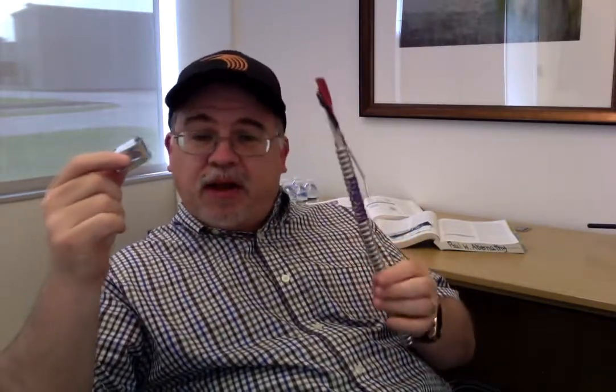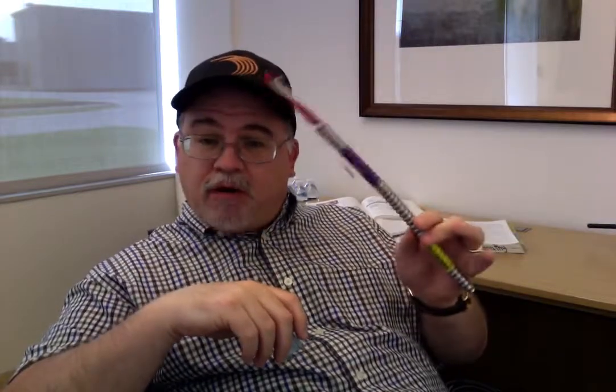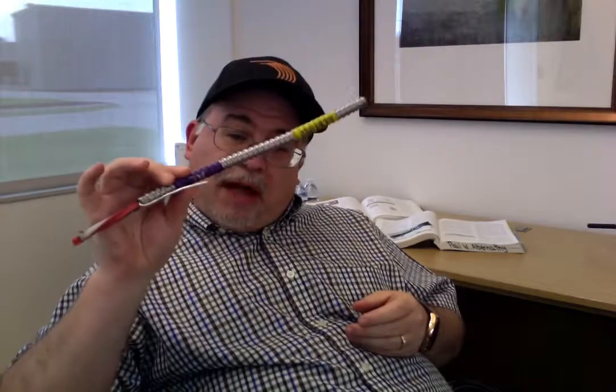Okay, so the other unique thing about this fitting is that it is good for AC cable, it is good for traditional MC cable, and it's good for the SmartGround enhanced type of product that's called MCI-A. So anytime you see a fitting that has MCI-A, then it is okay to use with an MC cable that's using the armor as an effective ground fault current path, like our SmartGround or even our healthcare facility type of SmartGround product. You need an MCI-A fitting. But the good news is this works on a bunch of different types of cables, AC, MC, and MCI-A. So that's a unique fitting.